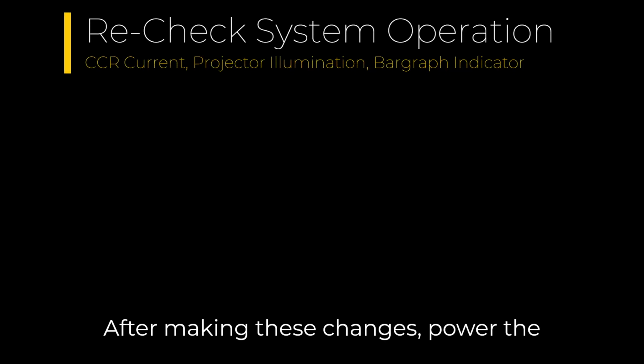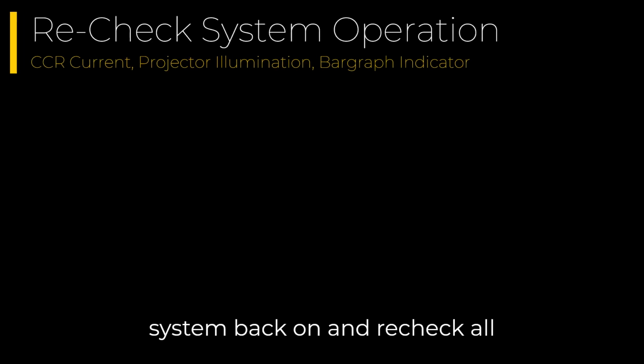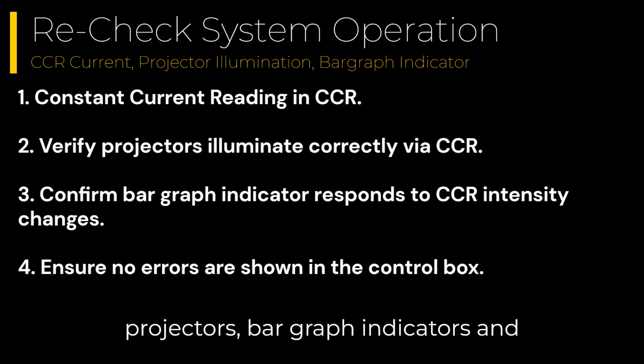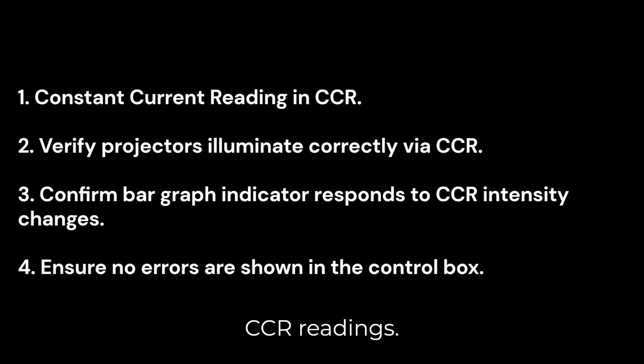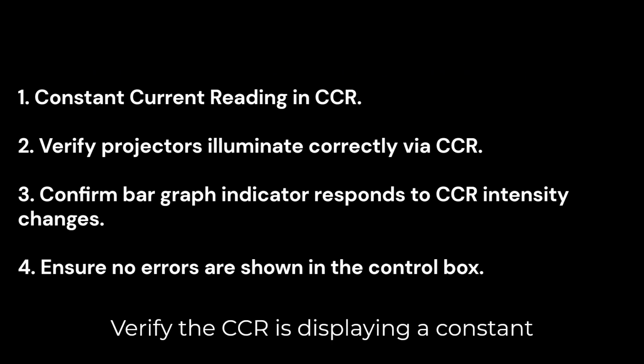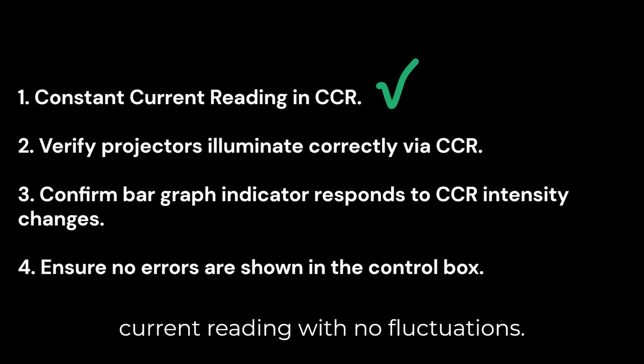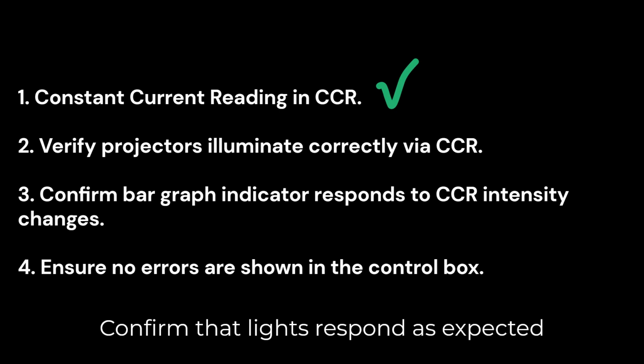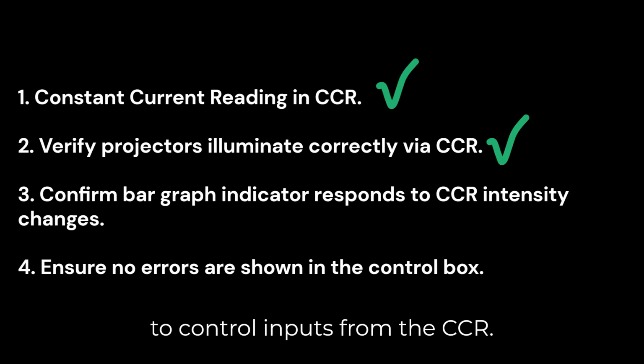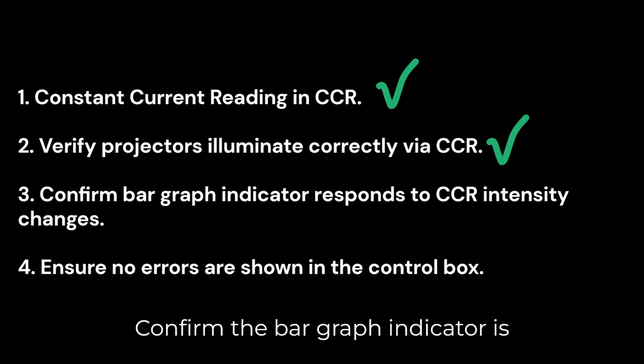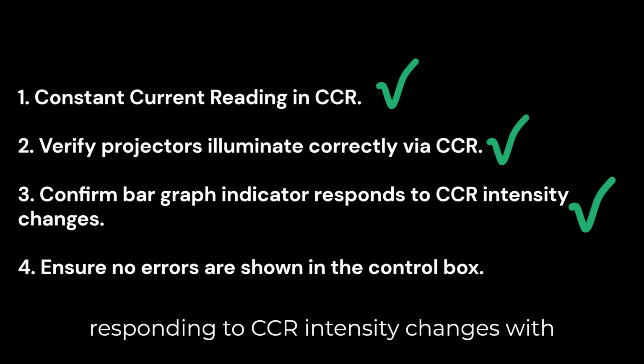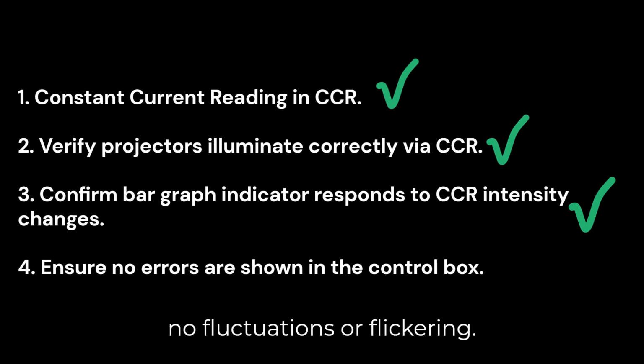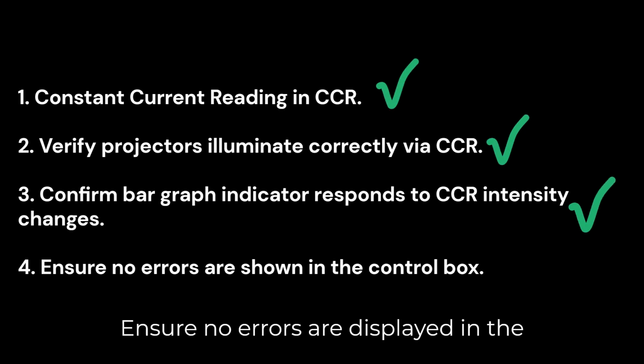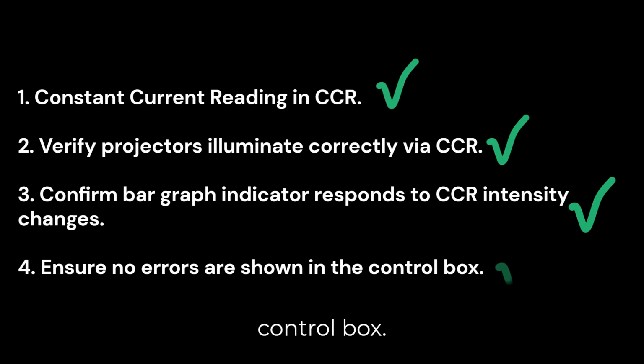After making these changes, power the system back on and recheck all projectors, bar graph indicators, and CCR readings. Verify the CCR is displaying a constant current reading with no fluctuations. Confirm that lights respond as expected to control inputs from the CCR. Confirm the bar graph indicator is responding to CCR intensity changes with no fluctuations or flickering. Ensure no errors are displayed in the control box.